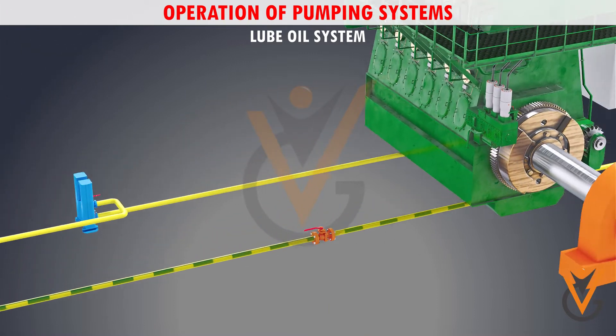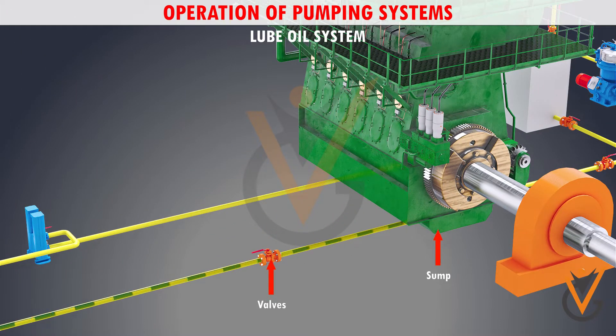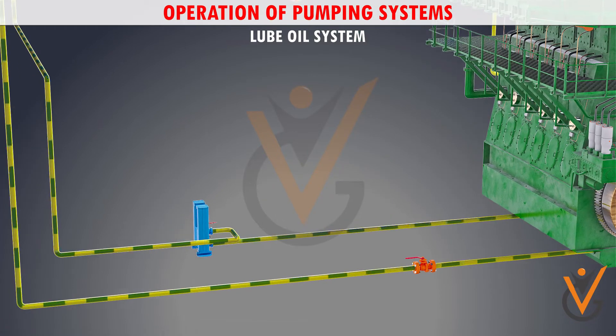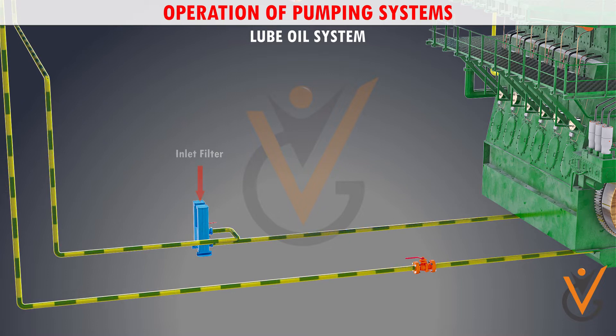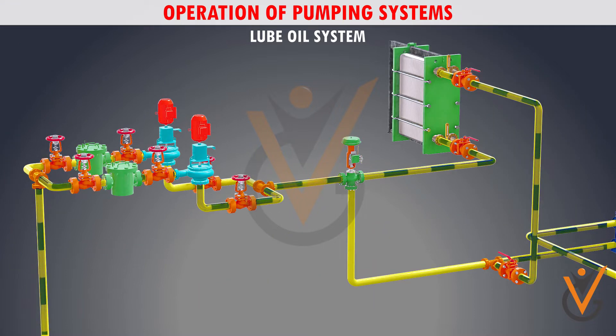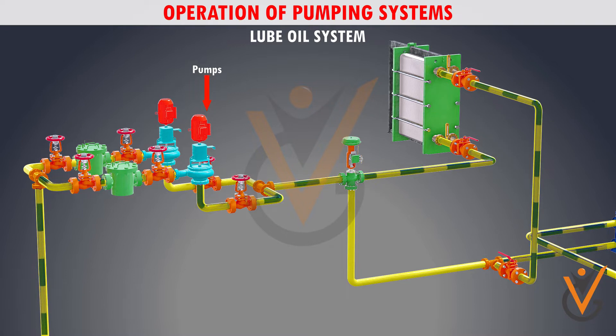The lube oil for lubrication is taken from the storage tank, which goes directly to the sump. The supply is controlled by valves fitted in the line. The main lube oil pumps take suction from the main engine sump tank via an inlet filter and discharge oil via the main lube oil cooler. One pump operates while the other is on standby, set for automatic cut-in should there be a pressure reduction or primary pump failure.